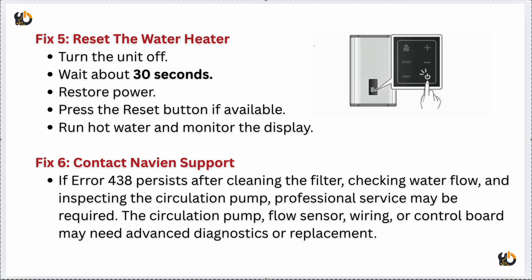Fix 6: contact Navien support. If error 438 persists after cleaning the filter, checking water flow, and inspecting the circulation pump, professional service may be required. The circulation pump, flow sensor, wiring, or control board may need advanced diagnosis or replacement.